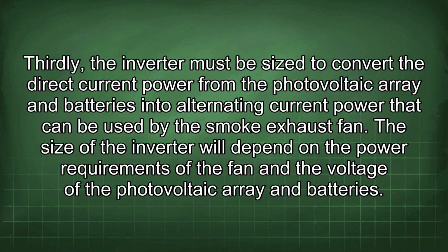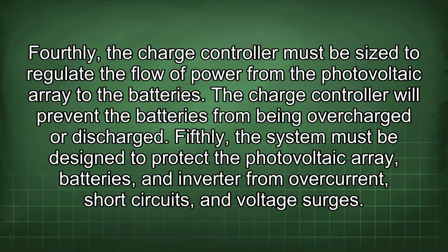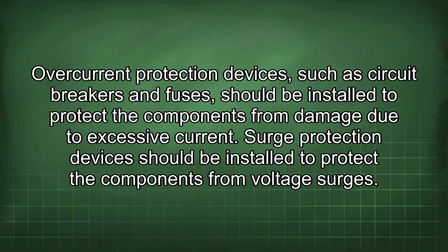The size of the inverter will depend on the power requirements of the fan and the voltage of the photovoltaic array and batteries. Fourthly, the charge controller must be sized to regulate the flow of power from the photovoltaic array to the batteries. The charge controller will prevent the batteries from being overcharged or over-discharged. Fifthly, the system must be designed to protect the photovoltaic array, batteries, and inverter from overcurrent, short circuits, and voltage surges. Overcurrent protection devices, such as circuit breakers and fuses, should be installed to protect the components from damage due to excessive current. Surge protection devices should be installed to protect the components from voltage surges.